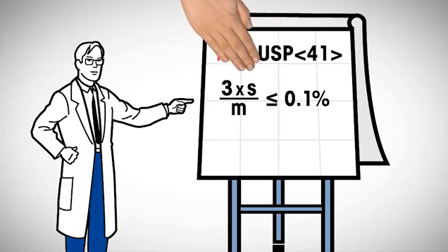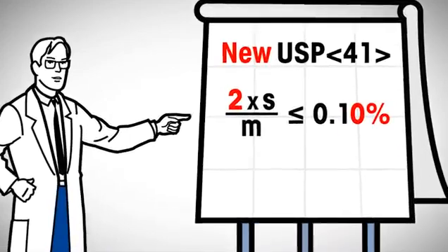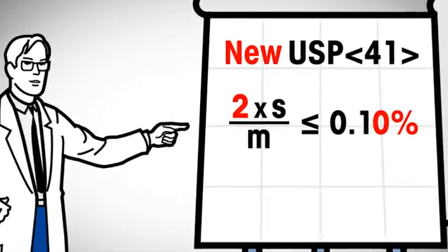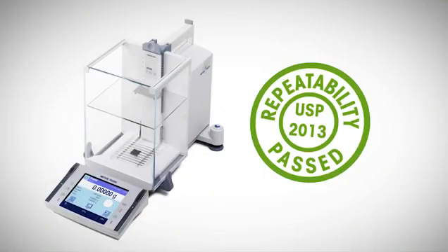In the new USP 41, first, the expansion factor goes down from 3 to 2. Second, the weighing tolerance changes from 0.1% to 0.10%, meaning a deliberalization of rounding. These two changes reflect current metrology practices and virtually compensate each other, so in most cases the minimum weight will remain unchanged.